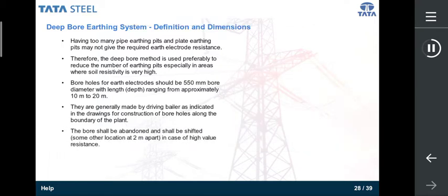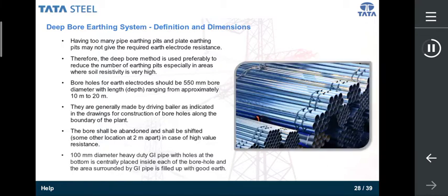The bore shall be abandoned and shifted to some other location 2 meters apart in case of high value resistance. A 100 mm diameter heavy duty GI pipe with holes at the bottom is centrally placed inside each of the bore holes, and the area surrounded by the GI pipe is filled up with good earth.